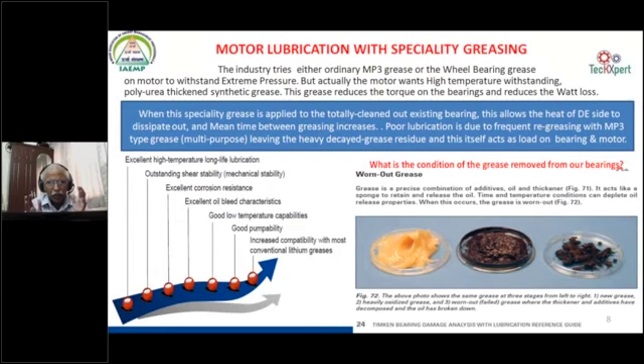I'm taking the aspect of TEFC, totally enclosed fan cooled motor, because this is used in IE1, IE2, IE3 everywhere. A motor needs excellent lubrication and at the same time very sufficient ventilation. Excellent lubrication means what? In this session I wanted to say what is happening in the industry and why this cannot be changed in the industry. At these post-COVID times, let us have the changes. The industry is happy with the ordinary multi-purpose grease, which is meant for ordinary usage, for 2 or 3 hours of running of motors per day. But we are running the motors for 24 hours.